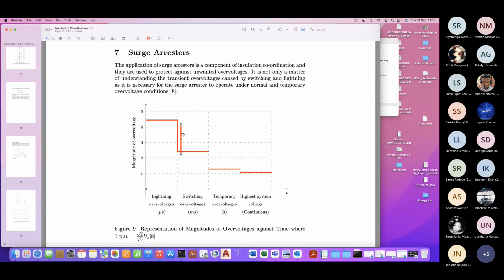So those are the overvoltages that a system experiences. The damaging ones are the lightning and switching overvoltages. Where your equipment will survive, because it's designed for it, are the temporary overvoltages and highest system voltage. So highest system voltage, we know that's a rating. Temporary overvoltages, if you think of the power frequency withstand in the table, that's what we're talking about there.